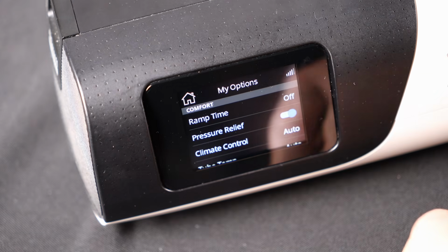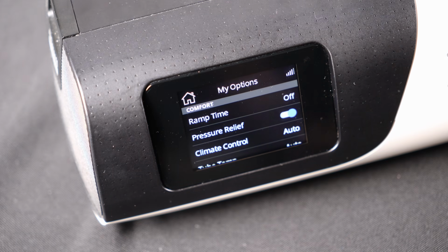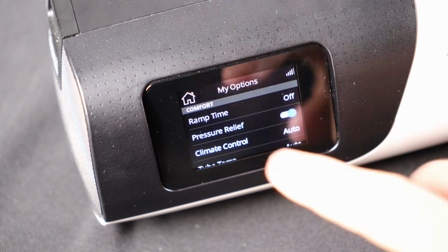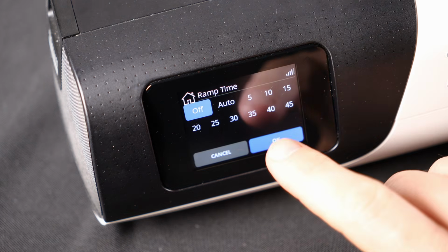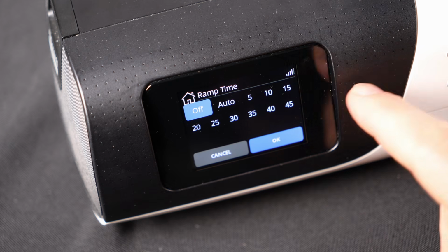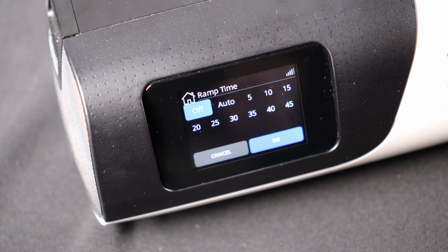So when you click on My Options, the very first thing you'll see there is ramp time. You see that I've turned ramp time off. What ramp time does is it starts the device at a lower pressure than what your standard start pressure is supposed to be for a period of time, whether that be, if we click on it here, 5 minutes, 10 minutes, up to 45 minutes, or set on automatic. What automatic means is it'll wait till you go to sleep, and once it detects that you're asleep, then it will go to your start pressure and then start treating you.